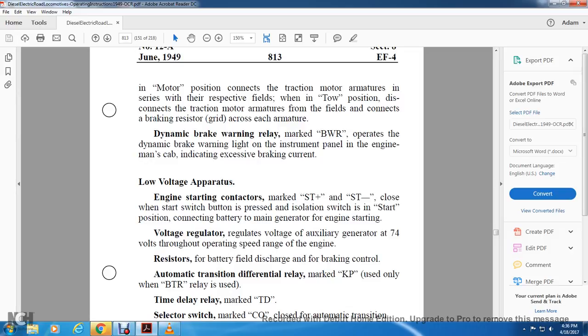Alright, the low voltage apparatus. Engine starting contactors, marked ST plus and ST minus, close when the start switch button is pressed, isolation switch in the start position, connecting the battery to the main generator for engine start. Voltage regulator regulates the auxiliary generator voltage at 74 volts through the operating speed range of the engine. Resistor, battery field discharge for the braking control. Automatic transition differential relay, marked KP, is used only when the BTR relay is used.